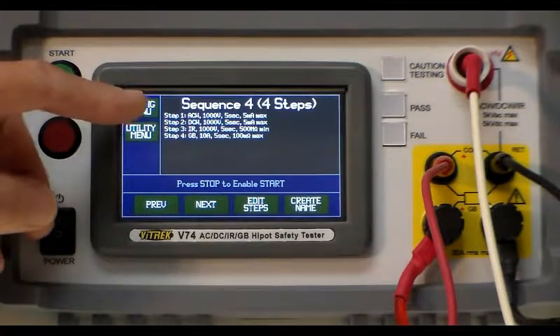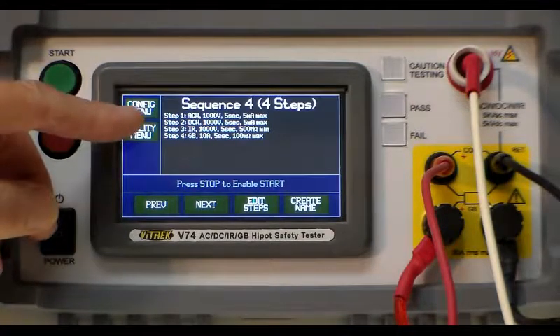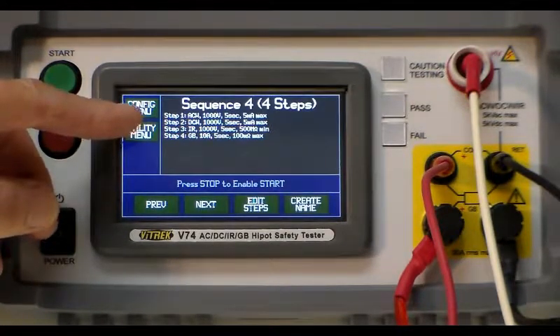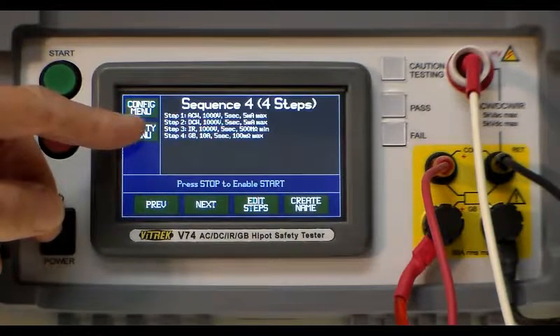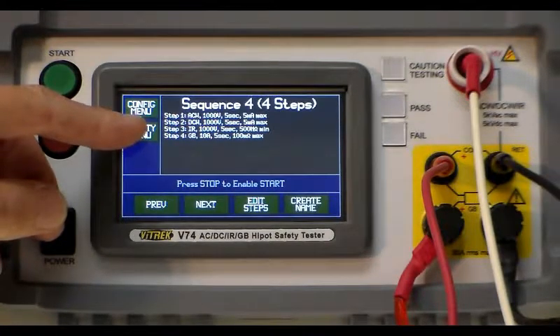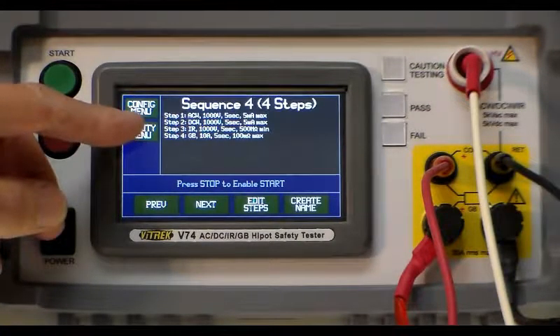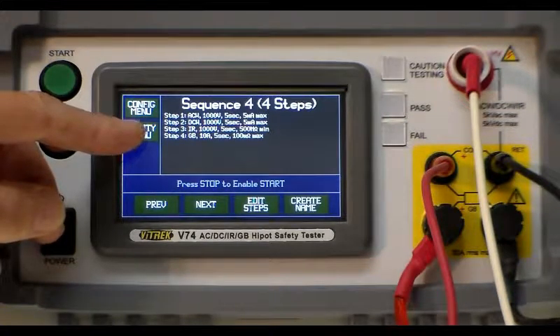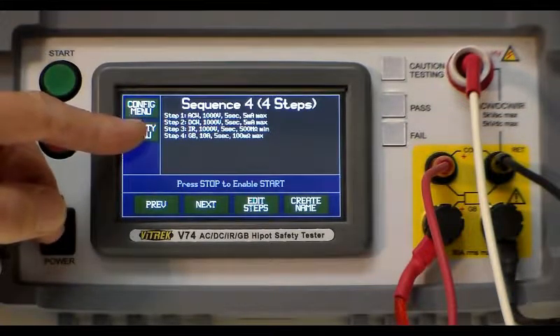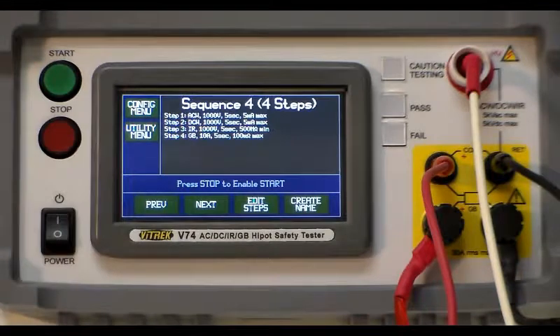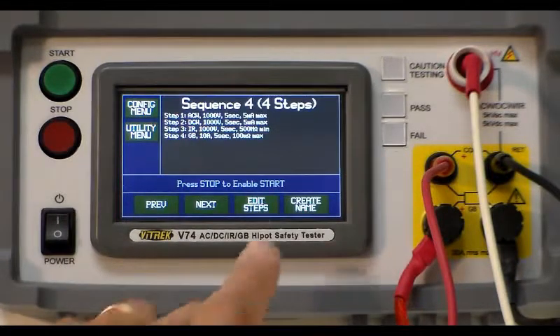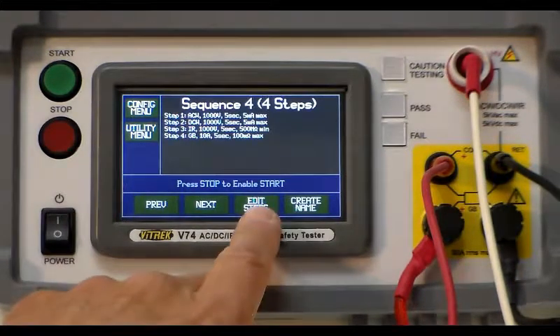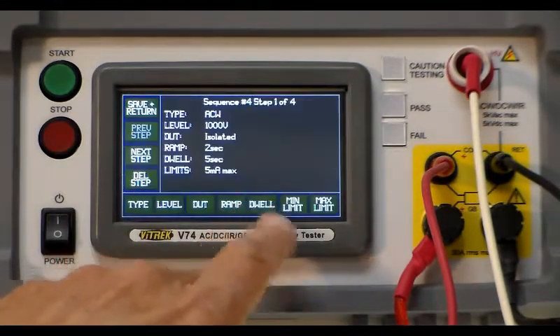ACW test at a thousand volts, DCW at a thousand volts, we're doing an IR test which is DC IR at a thousand volts and then we're doing a ground bond test at ten amps. We can go through all the steps on setting this up by hitting the edit steps button.